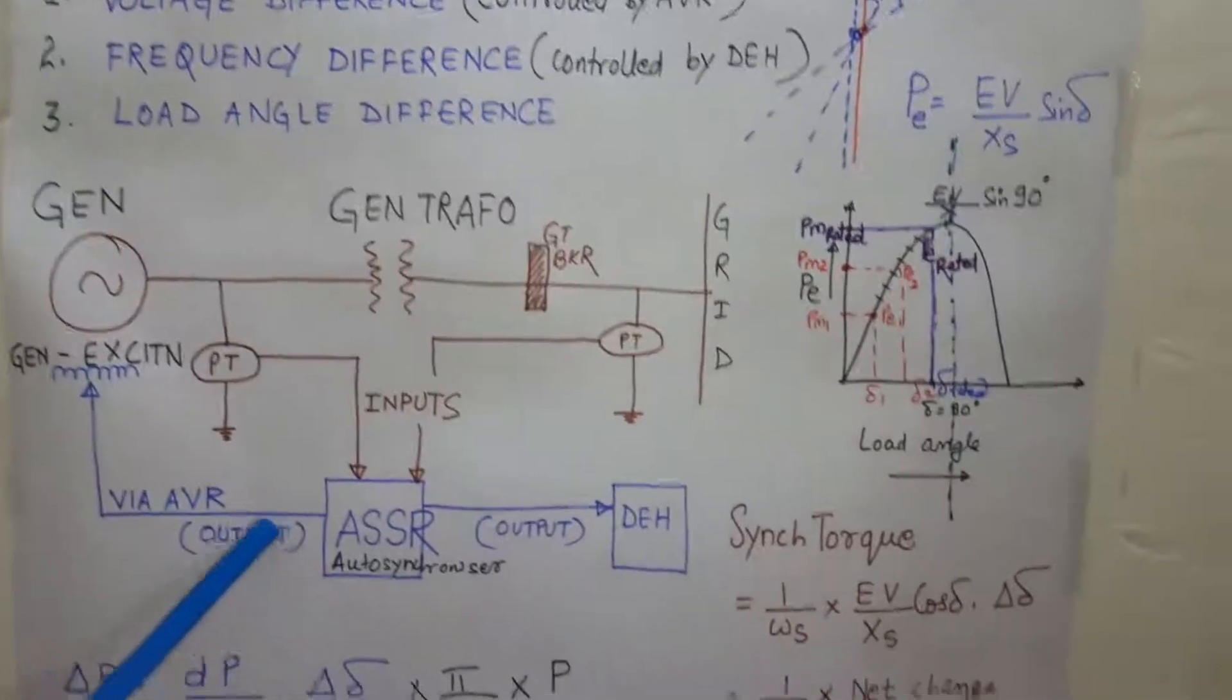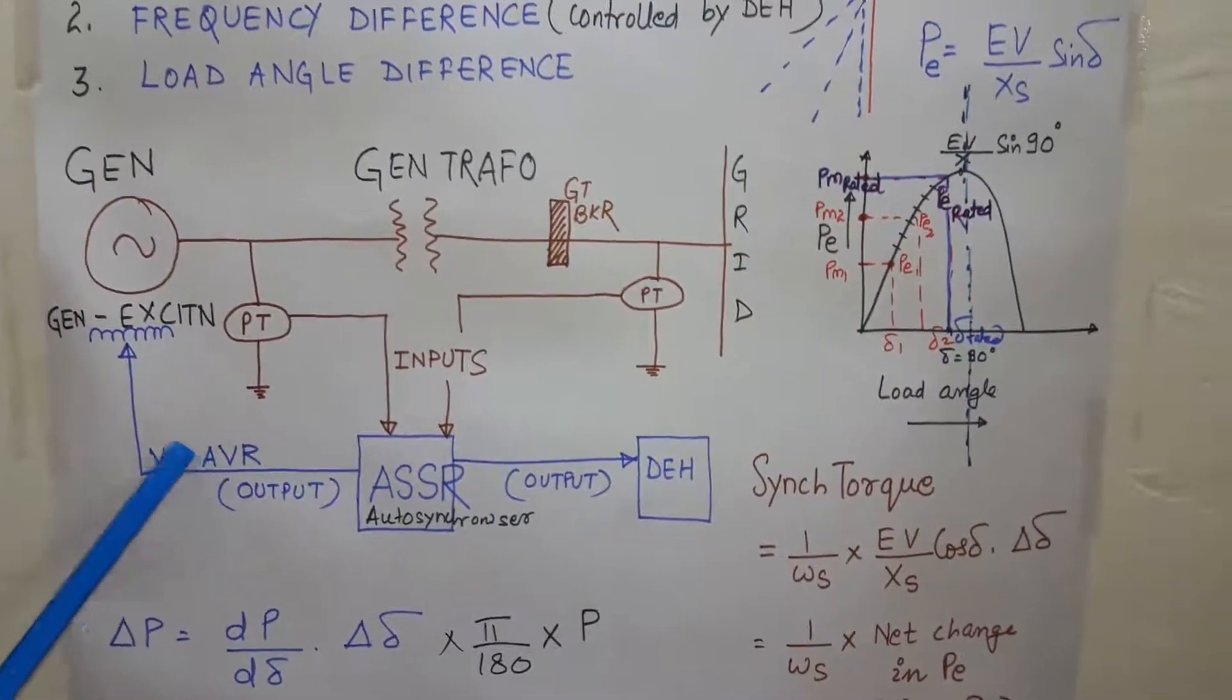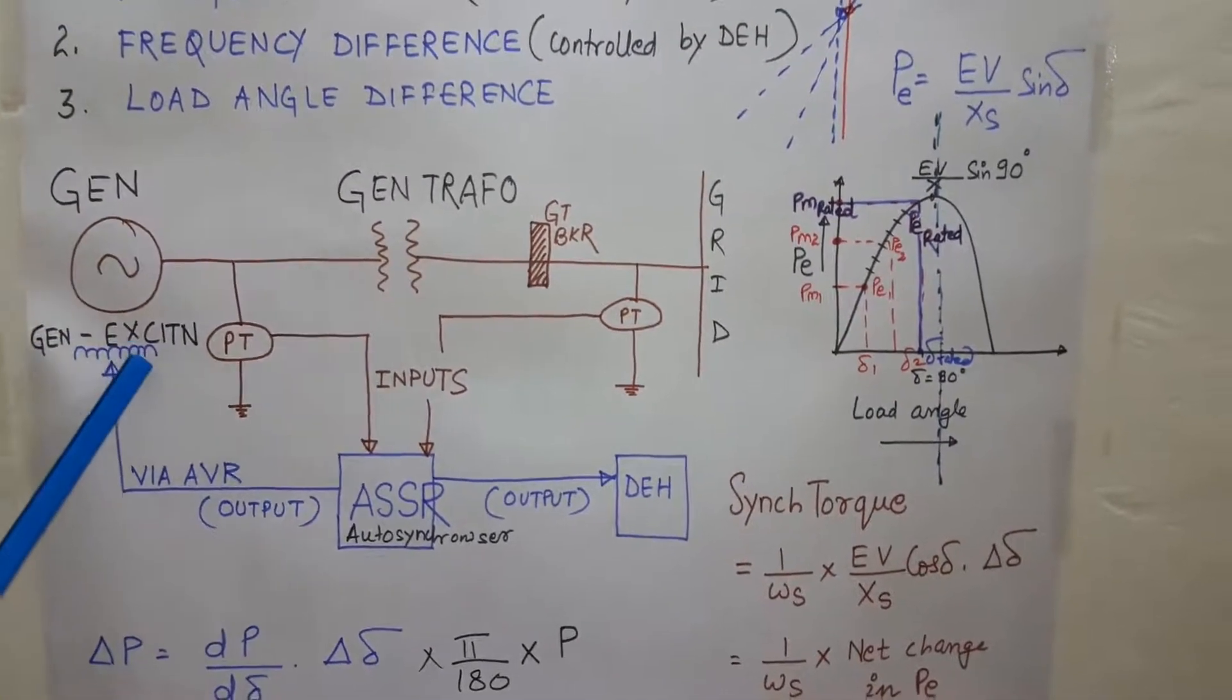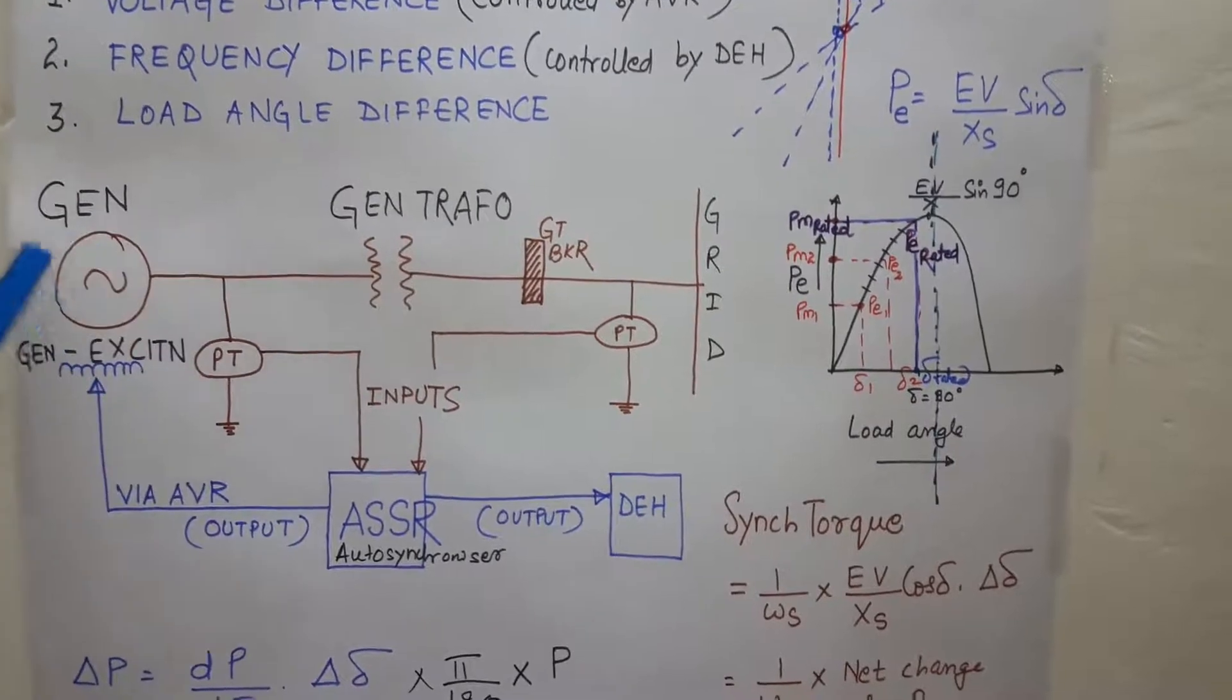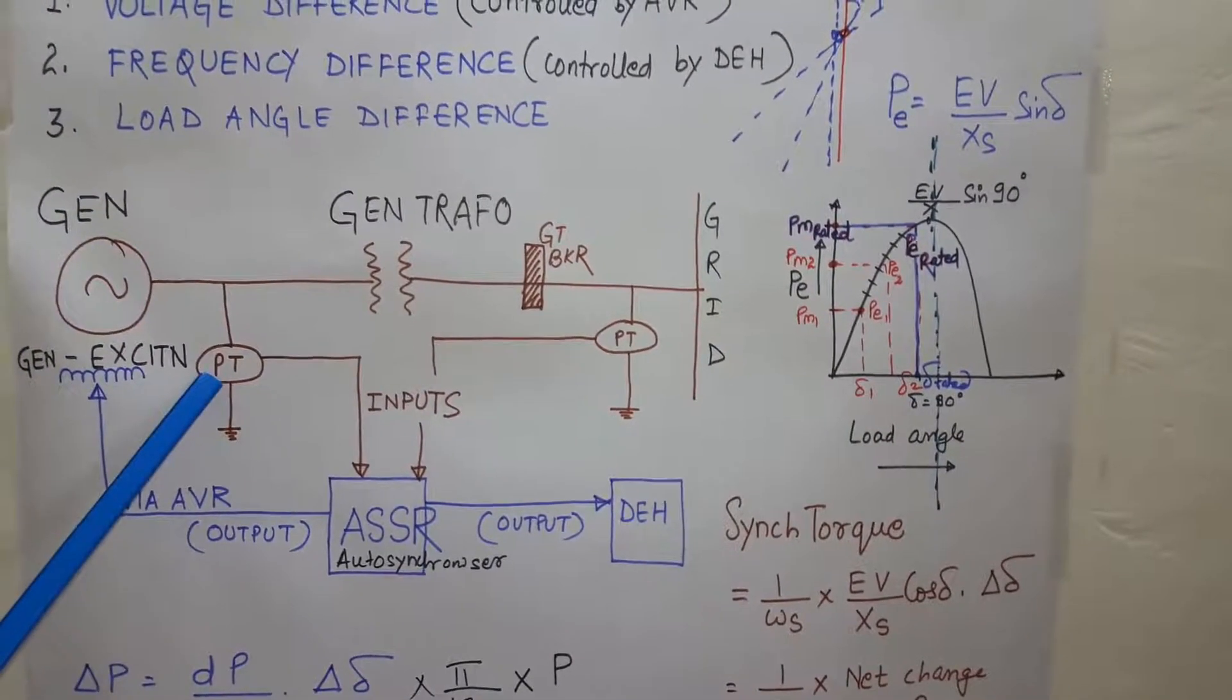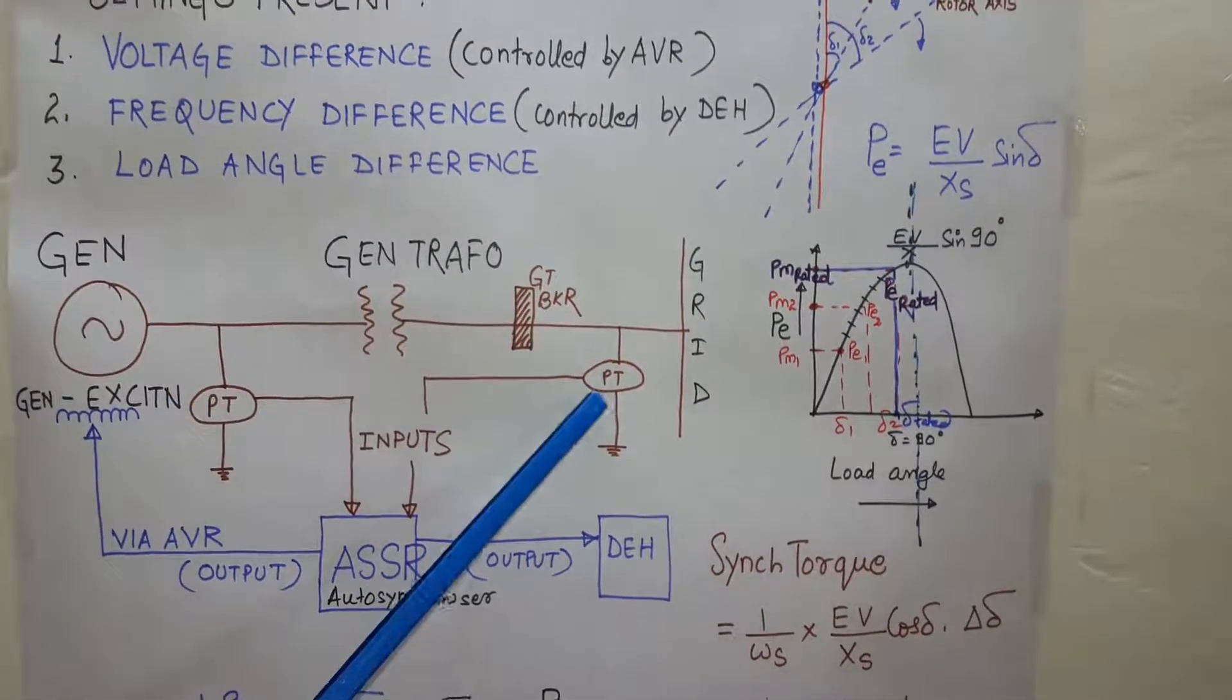When comparing, if the voltage is outside the tolerance limit of this setting, immediately it will send an output signal to the automatic voltage regulator to control the excitation current of the generator field winding. By controlling the excitation current, the generator voltage will be controlled and may come equal with the grid voltage.